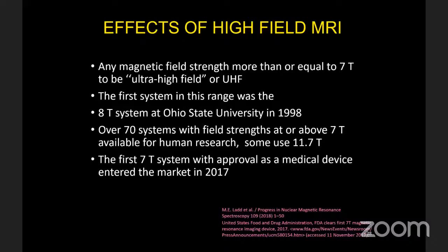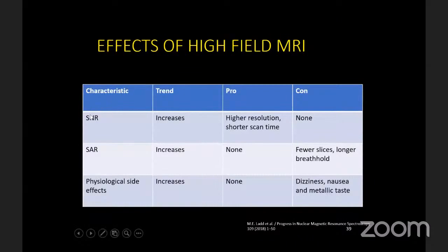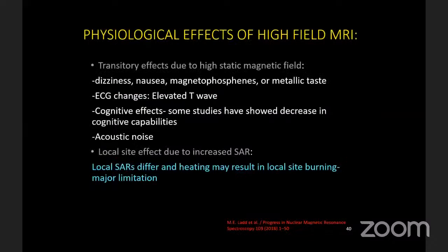What about high-field MR? Ultra-high-field (UHF) MR is generally considered above 7 Tesla. The first 8 Tesla system was installed at Ohio in 1998, and the first 7 Tesla system received approval as a medical device in 2017. When dealing with high-field magnetic strength, we consider signal-to-noise ratio, specific absorption rate, and physiological side effects. Physiological effects include transitory effects like dizziness, nausea, elevated T-waves, and acoustic noise. Local SAR can differ, and heating may result in local skin burns — a major limitation at high field strength.